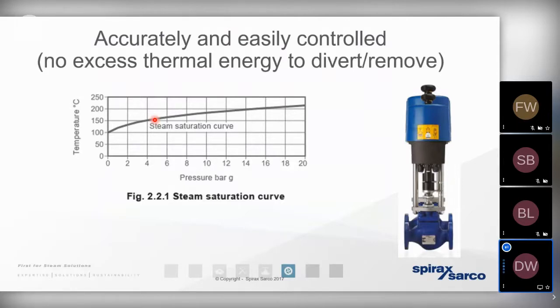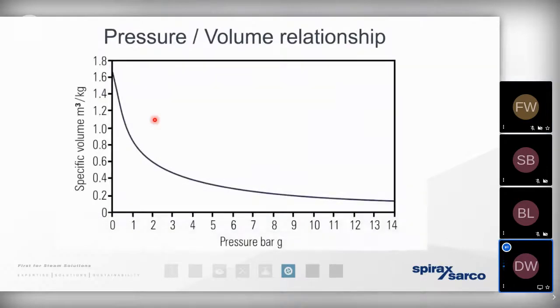For example, with a water to water system, we know that the water needs to be pumped across the heat exchanger. And we also know that we need to divert away any energy that isn't required by the process, hence the third port and that little circulating pump, neither of which are required on a steam to water heat exchange system. And we also need to remember that pressure to volume relationship that we've spoken about.